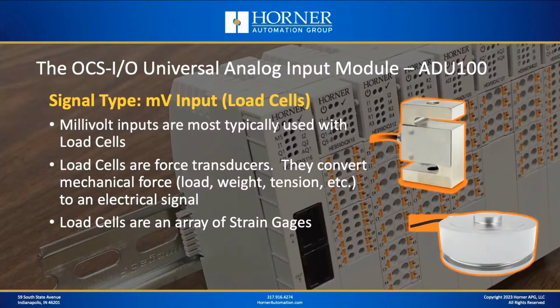Okay, now let's talk about millivolt input, which is supported by the ADU100. What are millivolt inputs typically used for? Well, the most common application would be load cells. Load cells are force transducers. So they are mechanical devices that convert force, which could be load, weight, tension, etc. They convert force to an electrical signal, which can be measured.